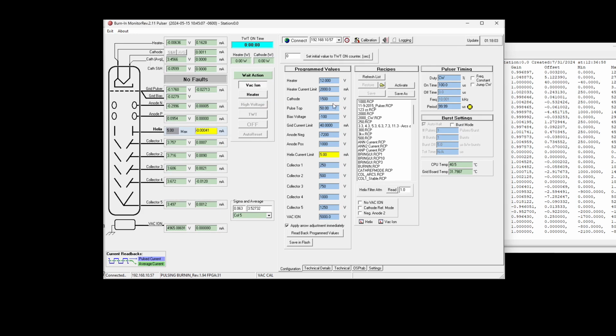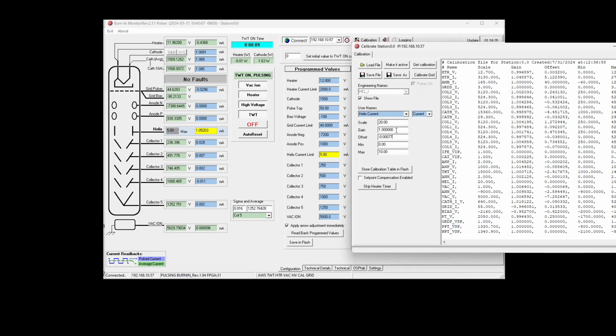We're starting at 1500 volts cathode. This is the lowest the cathode can run. Bypass heater timer, turn on high voltage. Still no current, and close the cathode switch. Now we see about 1 milliamp, 1.09 on the cathode, 1.05 on the Helix. This is uncalibrated.